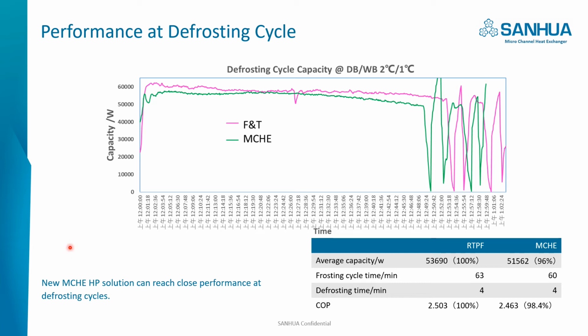We also tested the frosting condition performance. This chart shows the comparison of a fin tube heat exchanger and a microchannel condenser. In the frosting condition, that means dry bulb temperature 2 Celsius degrees and wet bulb 1 Celsius degree, this is the typical cycle time and the capacity we put together. The green one is microchannel. It's pretty close to the fin tube heat exchanger and much longer than the previous design.